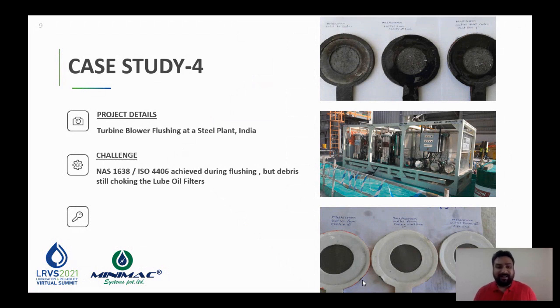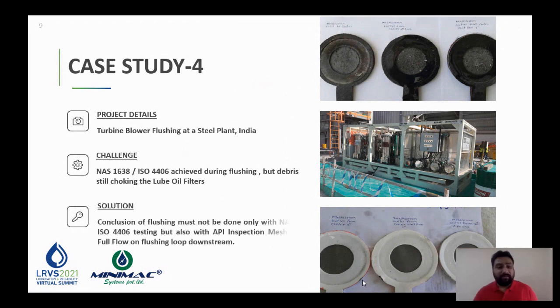Everyone was confused about where this debris came from, since they had already checked the NAS class and the ISO values. This confusion cost them 5 to 6 days of valuable project time. The reason was that testing under the NAS standard and ISO 4406 standard happens on a very small amount of oil sample, probably half a liter or less.